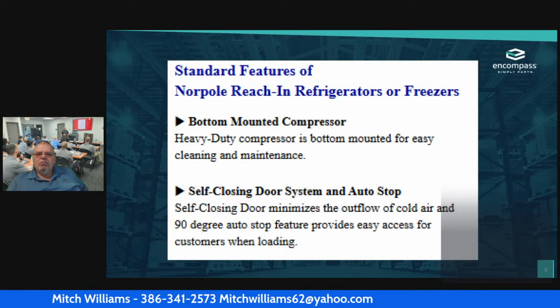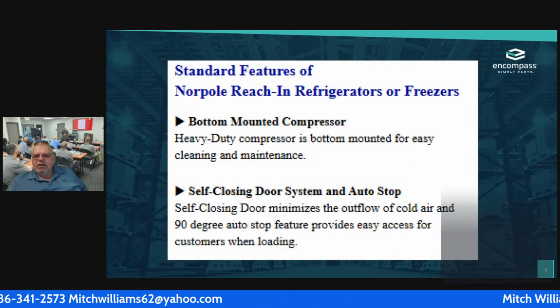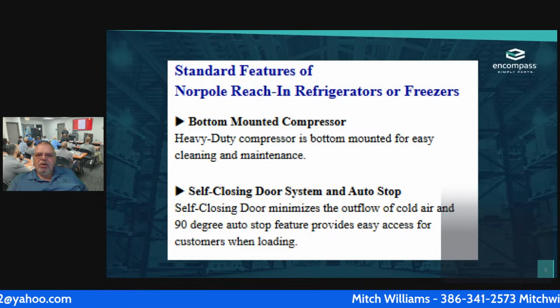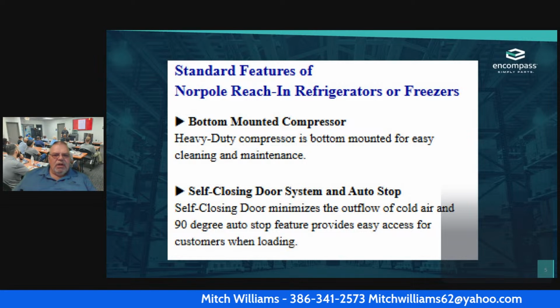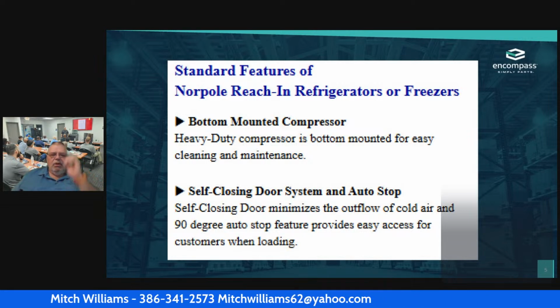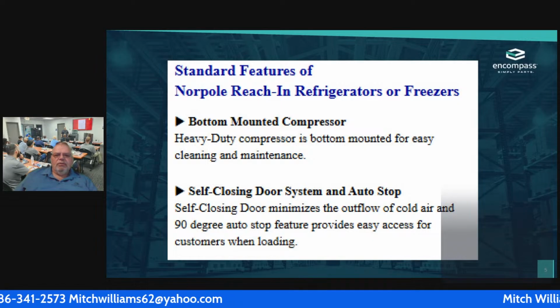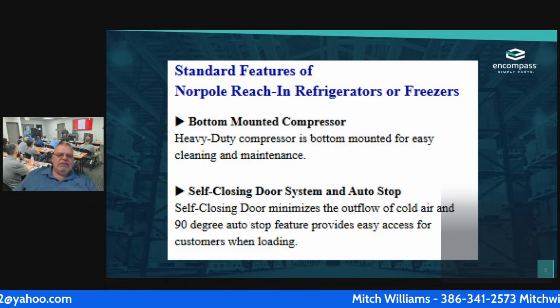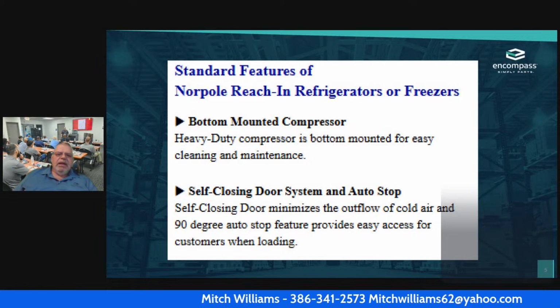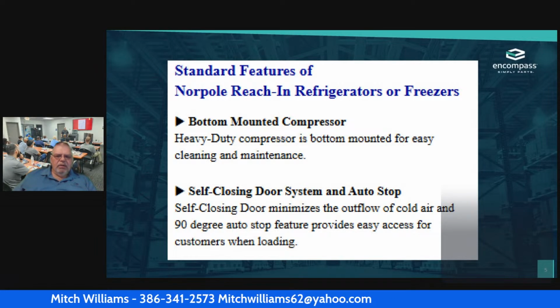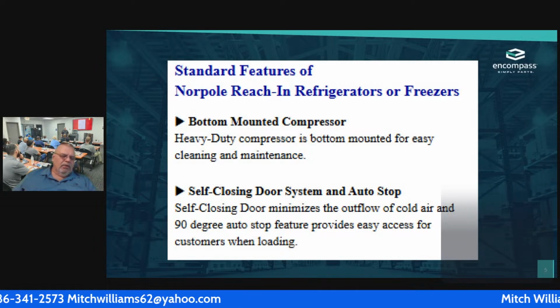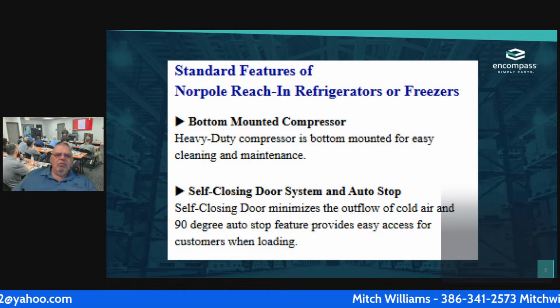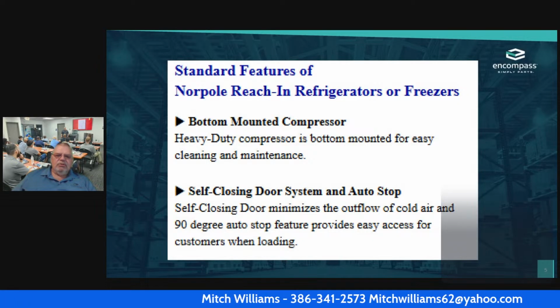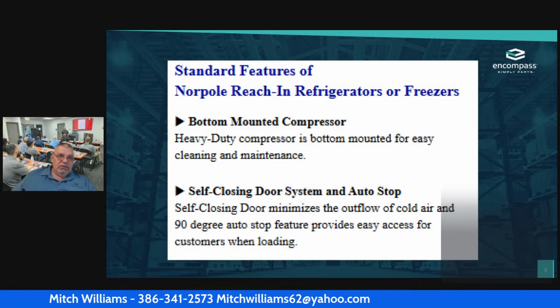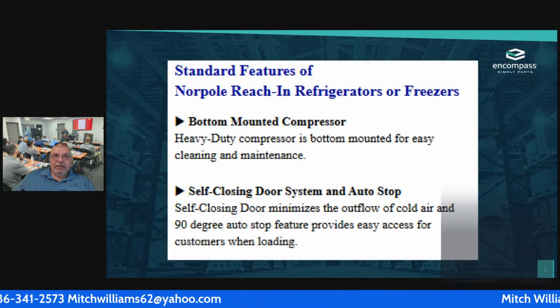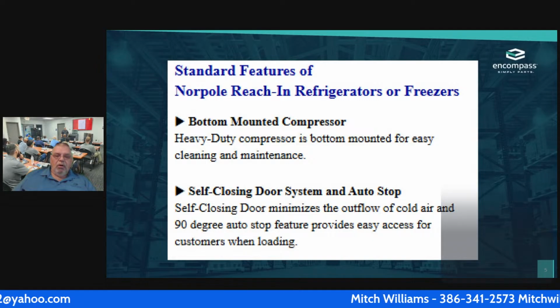Okay, so moving along, some of the standard features. I'm going to have to actually come out of my mode because for some reason it is not working properly. So the standard features of the Norpole reach-in refrigerator or freezer: once again, it has a bottom-mounted compressor. It has a heavy-duty compressor, and it's mounted in the bottom for easy cleaning and maintenance. The condensing coil is also down there, so it's a whole lot easier than having to get your step ladder, because you can't really see well if it's on the very top at that 70-inch mark.